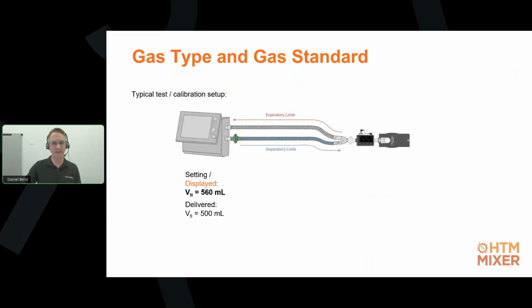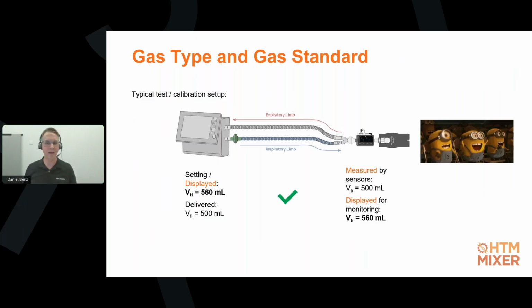Okay, back to our example, because if we set the same gas standard, then we also compare the same values with each other. So even though our gas flow analyzer measures just the 500 ml, if we set it to BTPS, the same standard used by our ventilator, then our displayed value is also going to be 560 ml, as the setting on the ventilator. Because now we are comparing apples with apples. Or maybe these guys here, probably more banana with banana.